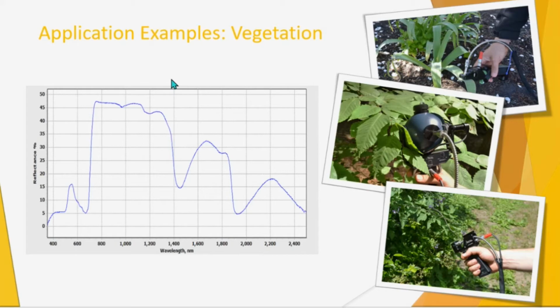So what that means is that the field of view of that fiber is a cone, and the full angle of that cone is 25 degrees. The farther away you will be from your target area, the bigger your sampling area will be. And as you get closer to your target, your sampling area will get smaller. So that is a bit limiting, if you want to do measurements at the leaf level.